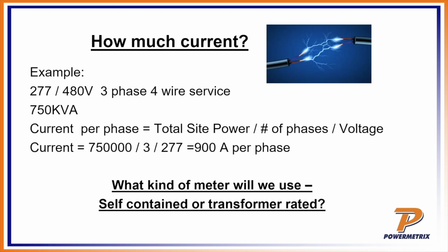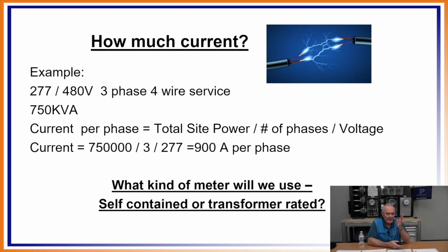So how much current? Let's look at an example here. Remember, current is going to be critical on this, because we have that break line where you can only go so high in current with those self-contained, and then I'm going to have to go to a transformer rated. So the amount of current is important, so let's look at how we get that. We've got an example here: 277/480 volt, 3-phase, 4-wire service. We've got a 750 kVA transformer, and we need to find the current per phase.